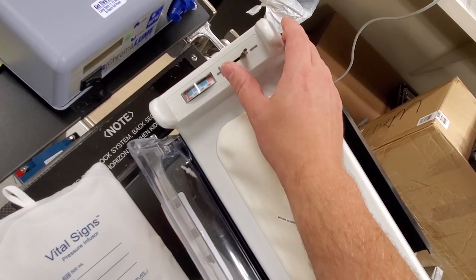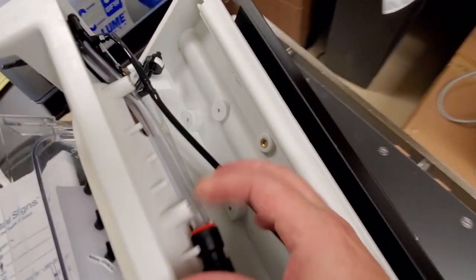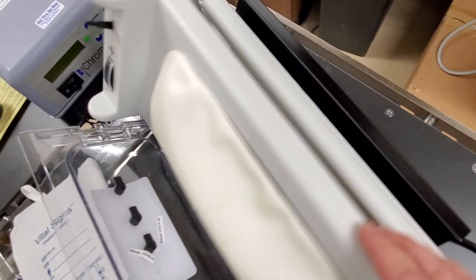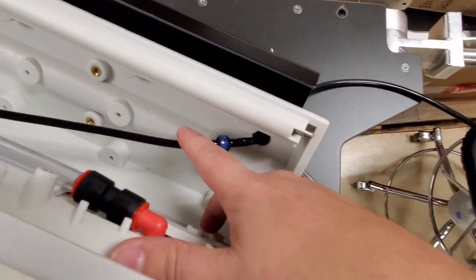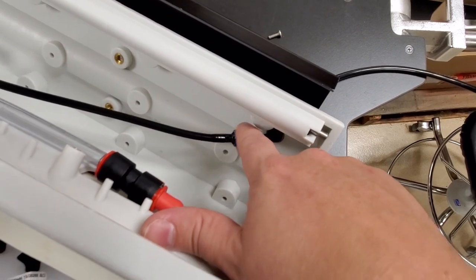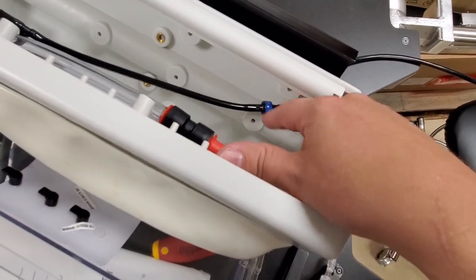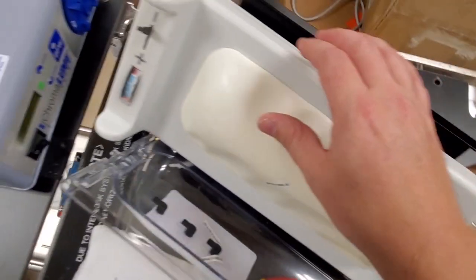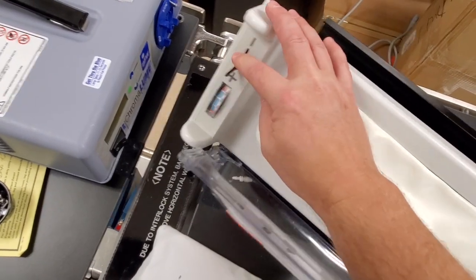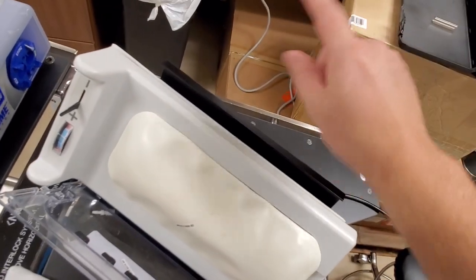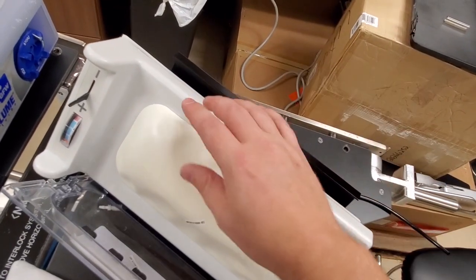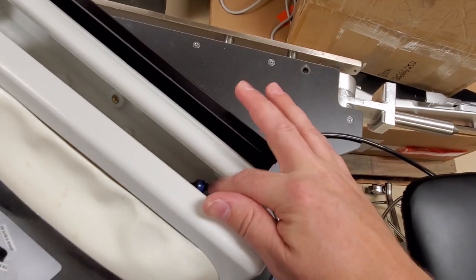So when you slide this guy over to the minus it then goes over here and vents it to atmosphere relieving the pressure. At no time does air go backwards this way from one reservoir to the other because of the check valve. So I could actually maintain pressure keeping it on plus while the other cylinder is going. Because in other words, if you popped a hole in one bag, it would leak pressure from this bag. But with that check valve, we don't have that problem.